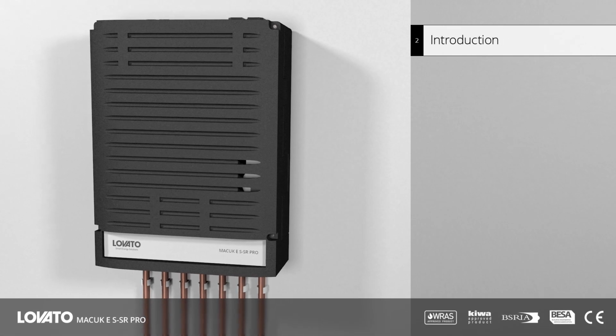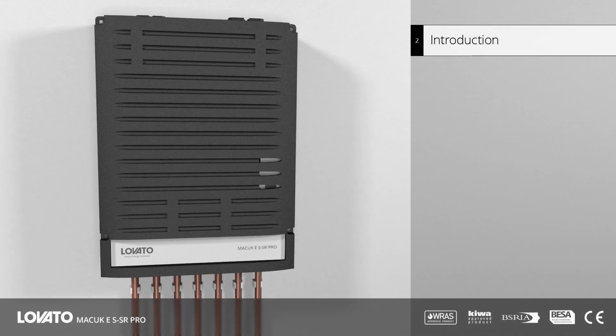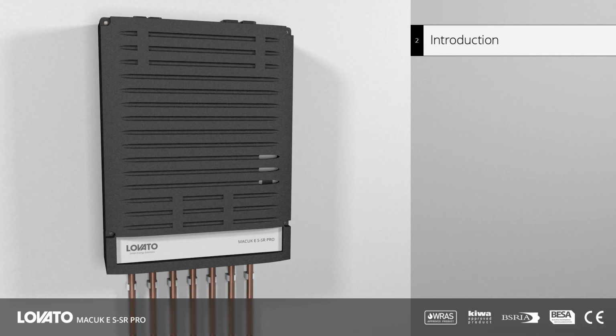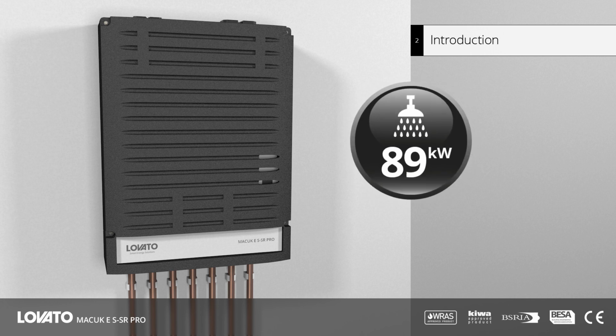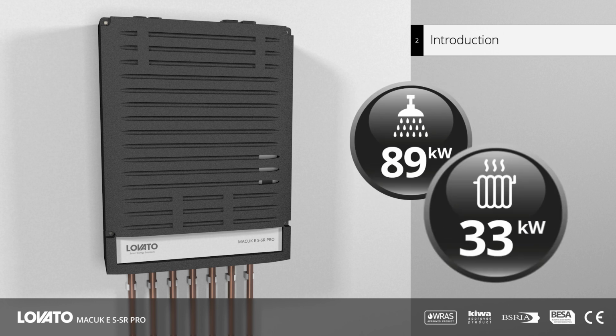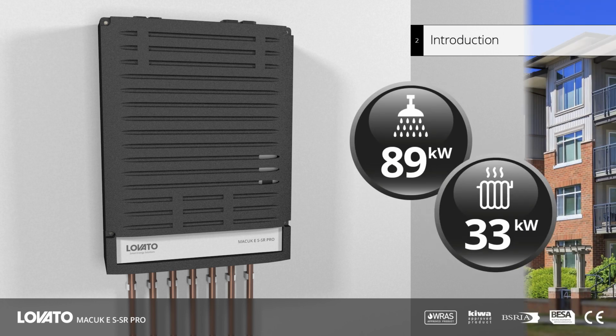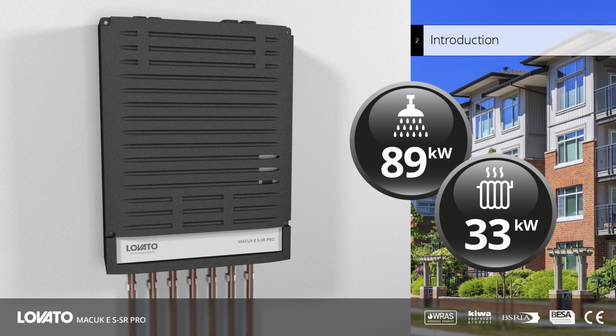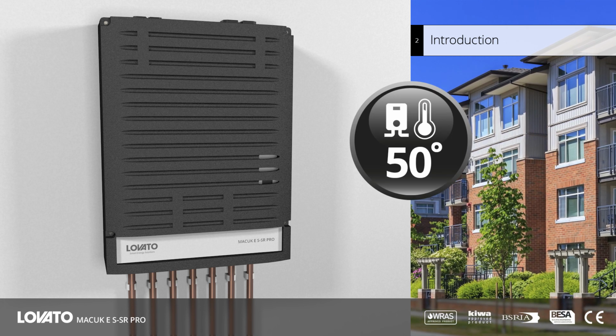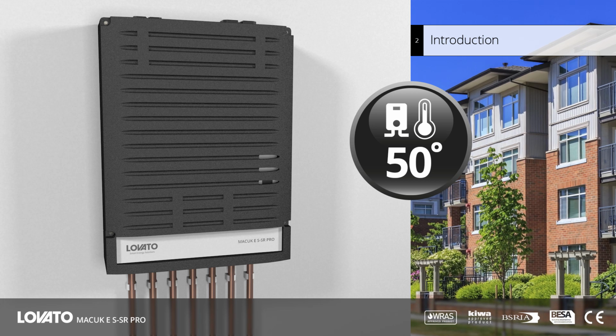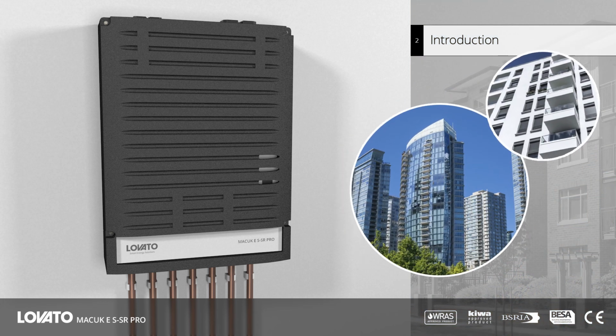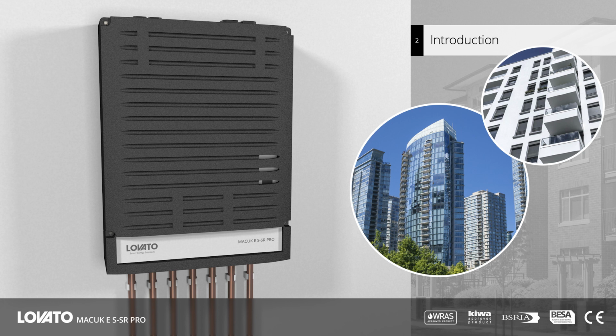The Lovato Macuk E is an indirect electronic heat interface unit available in multiple configurations with output capacities of up to 89 kilowatts for domestic hot water and 33 kilowatts for heating. Operating from primary temperatures as low as 50 degrees, it is perfectly suited to multi-occupancy situations in the case of tower blocks and high-density residential areas, where communal and district heating systems are installed.